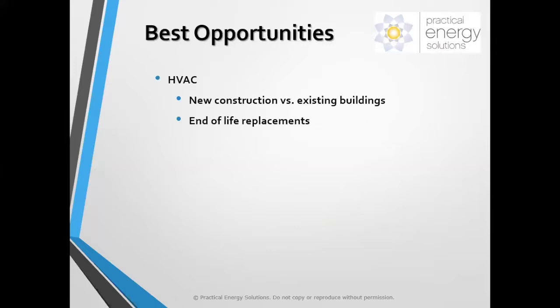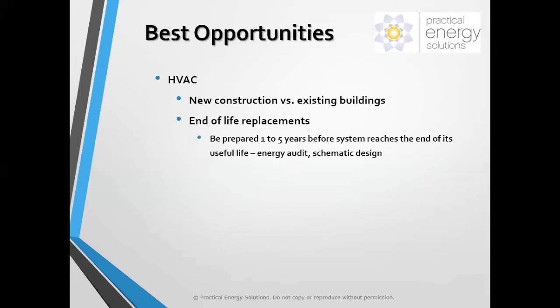That changes for an existing building when the system is at the end of its service life—say you have a 25-year-old boiler starting to cause problems and break down. You have to replace it anyway, so no matter what you do, you're paying something for a boiler replacement. If you get the minimum efficiency boiler, say it costs $10,000, you'll get about 80% efficiency. If you instead invested in something at 97% efficiency, maybe costing $3,000 more, you'd make up that cost difference within a few years, helping pay for the higher efficiency investment.